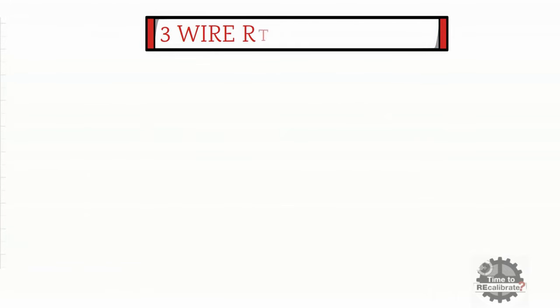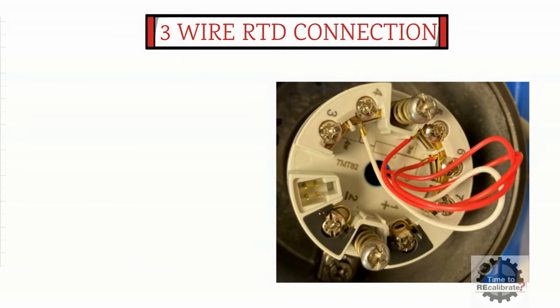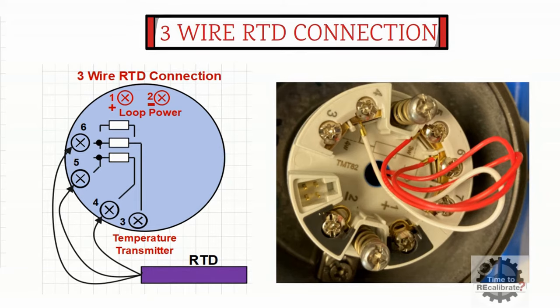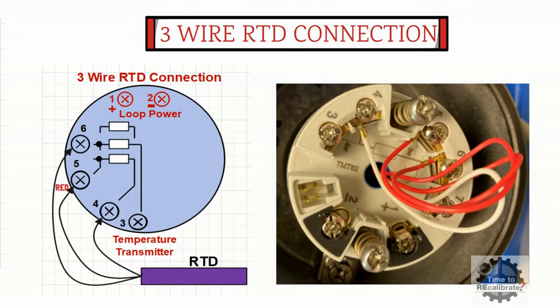In this section, I am going to show how to connect 3-wire RTD to a temperature transmitter. As the name suggests, 3-wire RTD has 3 cables: 2 red cables and 1 white cable. To connect 3-wire RTD to the temperature transmitter, connect one of the red cables to terminal number 5 and another red cable to terminal number 6. After this, connect the white cable to terminal number 4 of the temperature transmitter. Once you are done with the RTD connection, turn on the loop power supply and check the reading on the display.